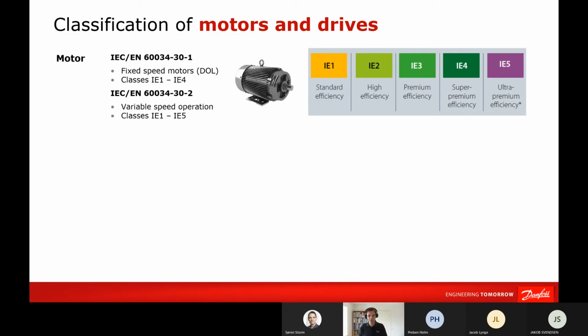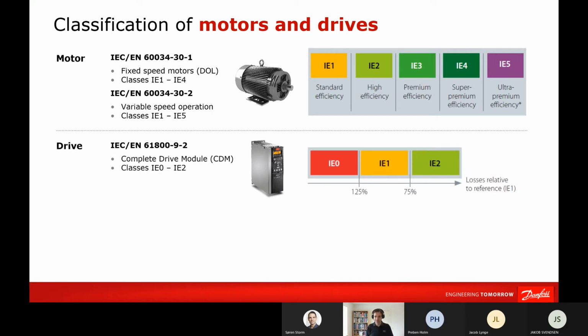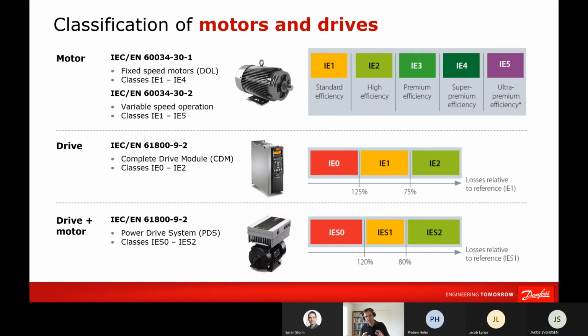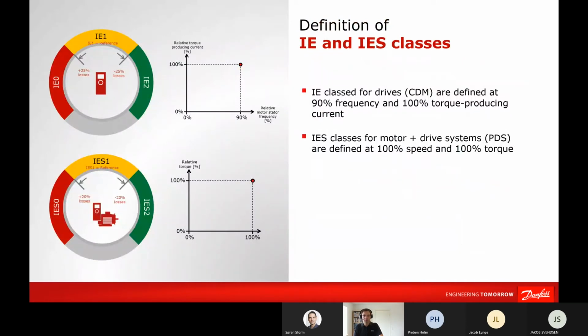It is well known that motors are classified in efficiency classes. The classes go from IE1 to IE4 for direct online motors like induction motors, and up to IE5 for motors for variable speed operation. Now, similar to these classes, there are defined three classes for drives. The classes go from IE0 to IE2. And also there are defined classes for drive plus motor, so for drive motor systems. And these classes are called IES, and they go from IES0 to IES2. The way these classes are determined is a bit different between a drive and the motor drive system, the power drive system, how we call it, because the definition points are a bit different.